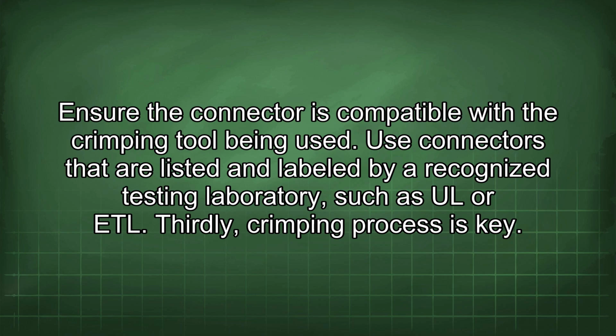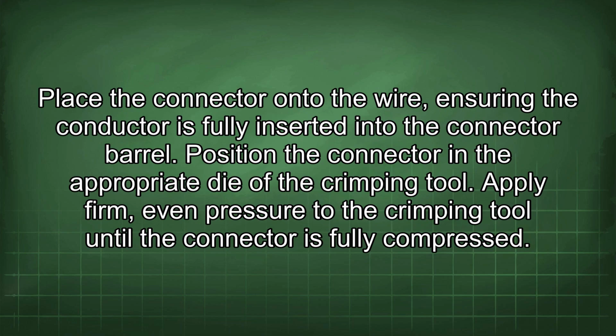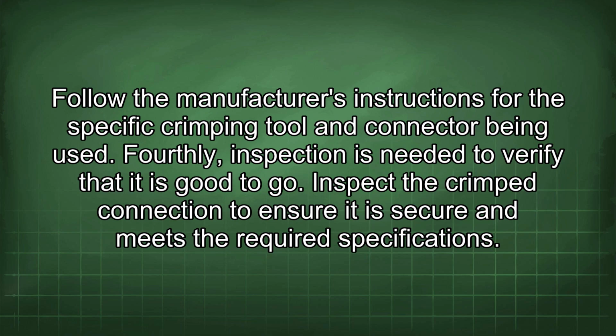Thirdly, the crimping process is key. Place the connector onto the wire, ensuring the conductor is fully inserted into the connector barrel. Position the connector in the appropriate die of the crimping tool. Apply firm, even pressure to the crimping tool until the connector is fully compressed. Follow the manufacturer's instructions for the specific crimping tool and connector being used.